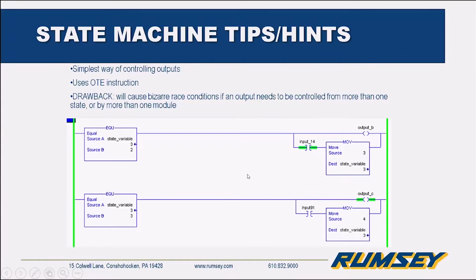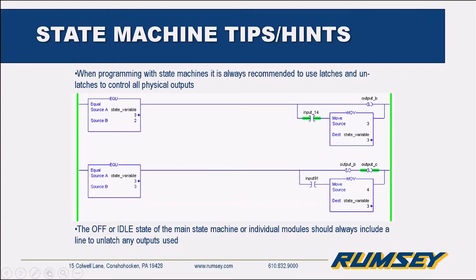The simplest way to use a state machine for controlling inputs and outputs would literally be using the OTE instruction. Turn on the output, wait for the input, move on to the next state. The big drawback to doing this would be if you need to control the outputs from more than one state or more than one module, there's going to be racing in the PLC program as to who would have control over that. And we know it's generally not a good idea, actually it doesn't really work that well, to use multiple OTEs to the same output in the same program. So it's highly recommended that, if you're turning on discrete outputs, to use latching and unlatching with those outputs.